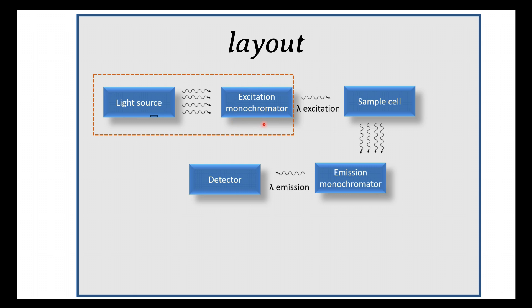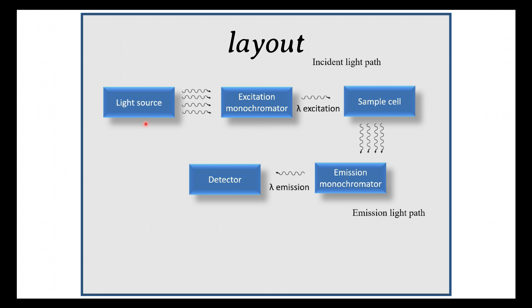Generally, xenon arc lamps are used as the light source, as their high brightness is essential to measure the weak fluorescence emission. The sample is illuminated by the chosen excitation wavelength, which causes it to fluoresce. The emission is collected by the emission monochromator, which is oriented at 90 degrees to the excitation monochromator, and the selected wavelength reaches the detector.